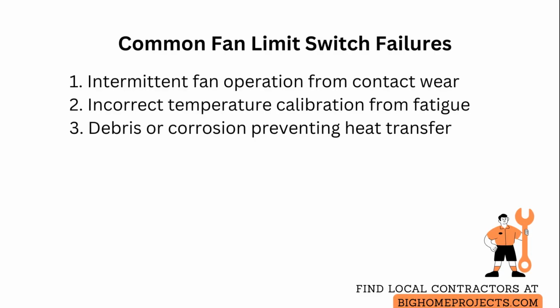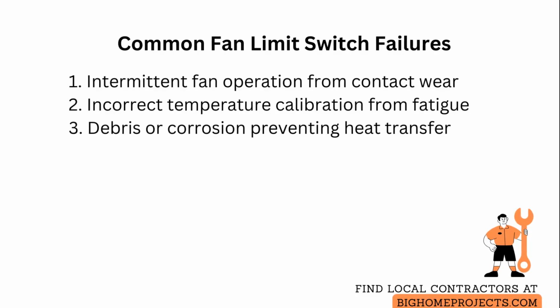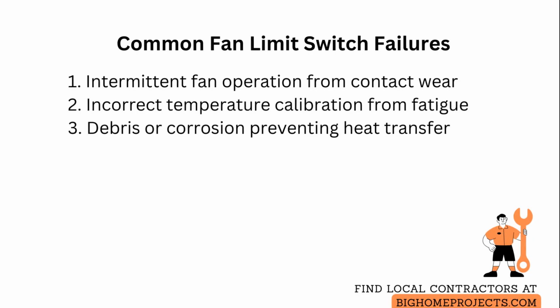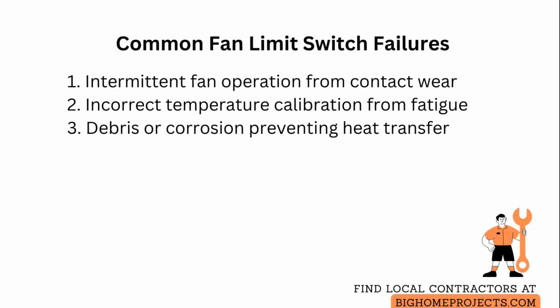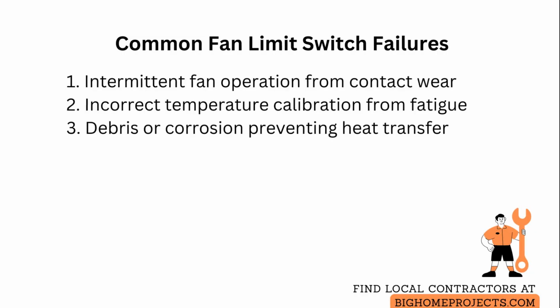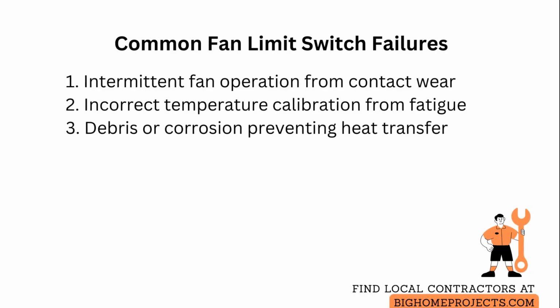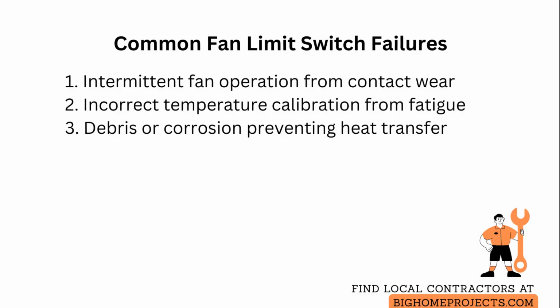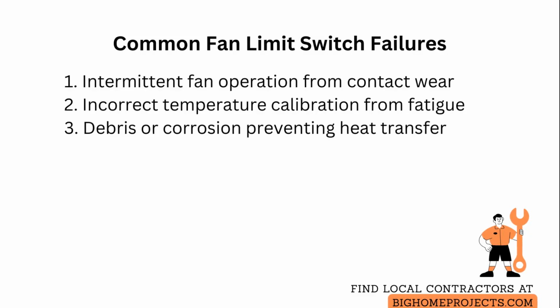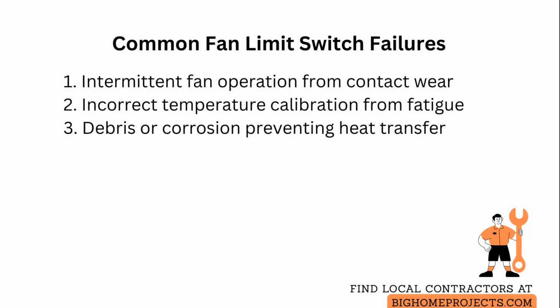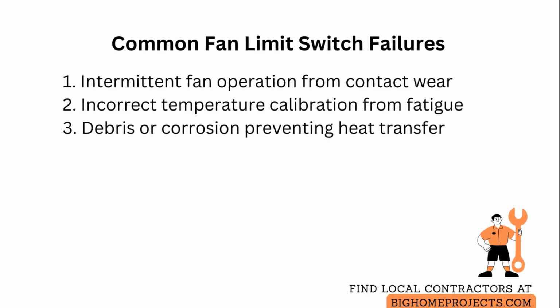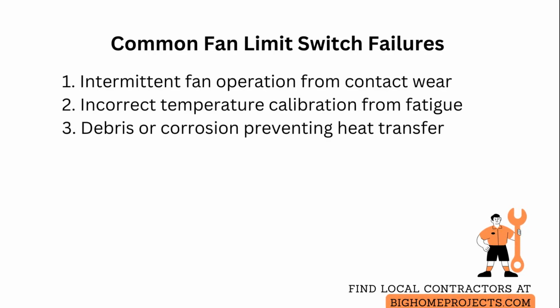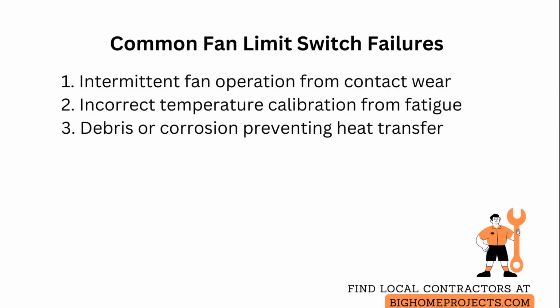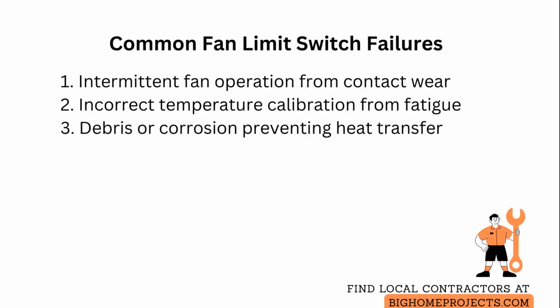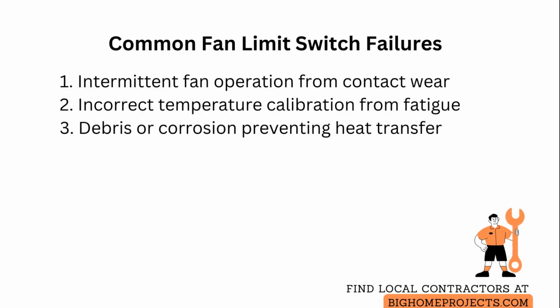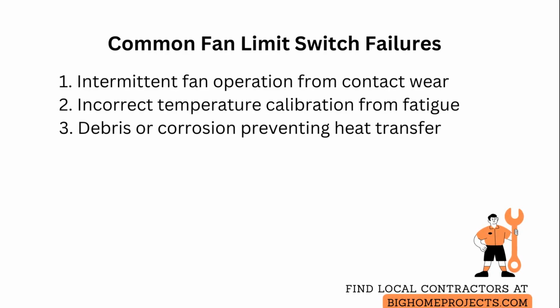Common issues include intermittent fan operation from partial contact wear, which can be diagnosed by cycling the system while monitoring continuity and replaced if contacts pit. Incorrect temperature calibration from material fatigue is resolved only by replacing the bimetal element with a matching specification part. And false positives, where debris or corrosion on the element body prevents proper heat transfer, so cleaning and ensuring good physical placement are required, but if performance does not return, replace the entire control rather than relying on bandage fixes.